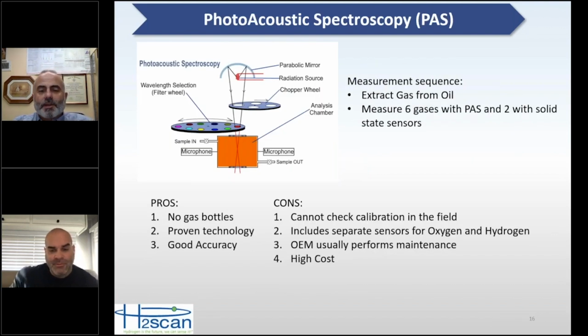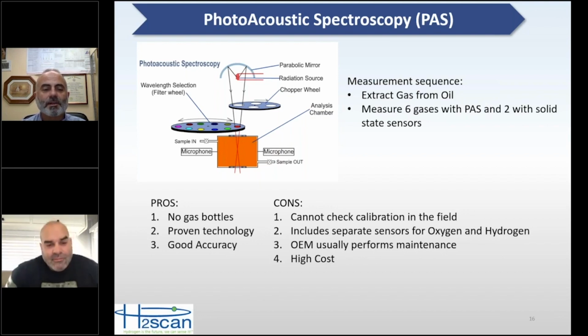Okay, photoacoustic spectroscopy. This is also a very popular method to use in online multi-gas monitors today. The way this technology works is there's an infrared light source. That light is shined through a light filter. Once the gas is extracted from the oil, the gas passes through the analysis chamber. When that light shines on the gas sample, there's a different light filter for each gas. So while it's looking for, say, acetylene, any acetylene molecules in the chamber will absorb the energy from that light.